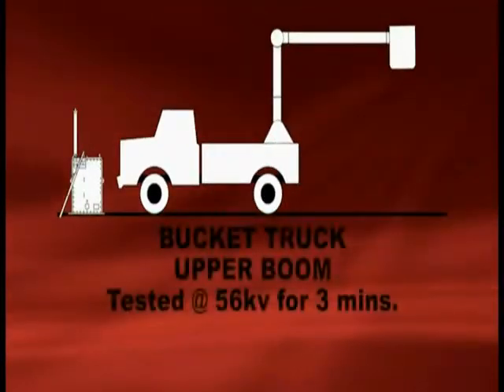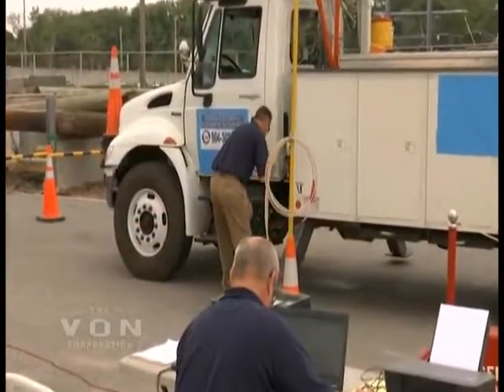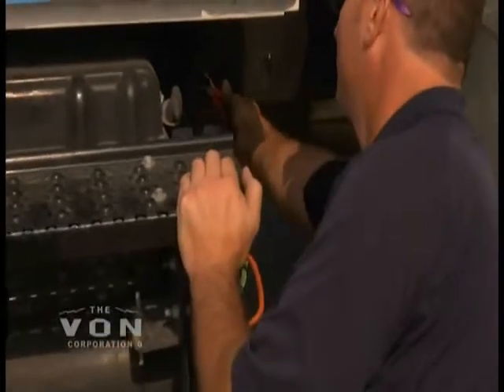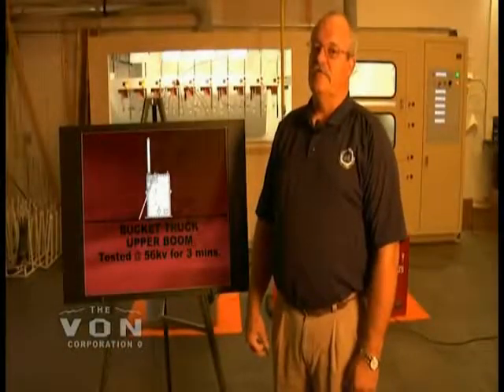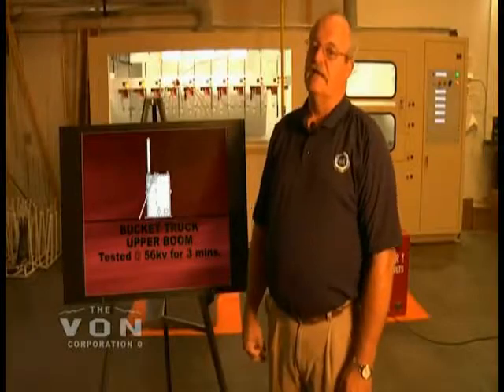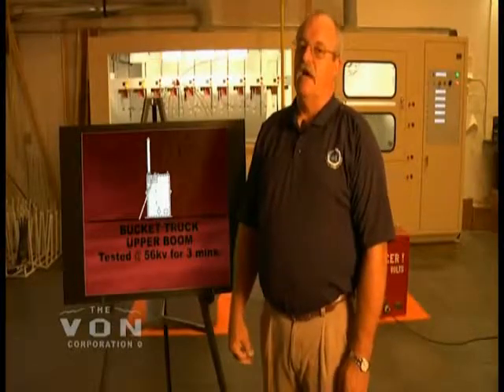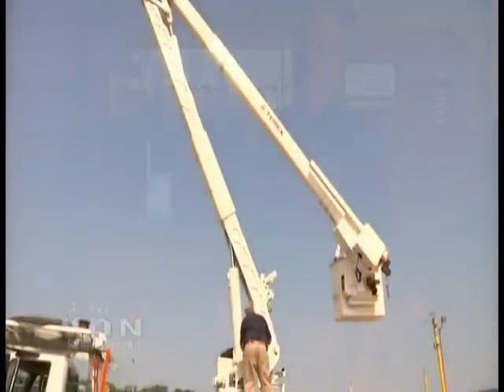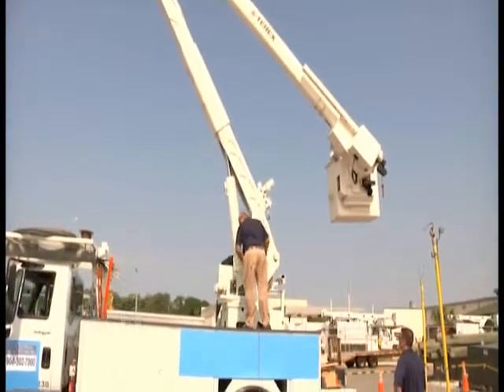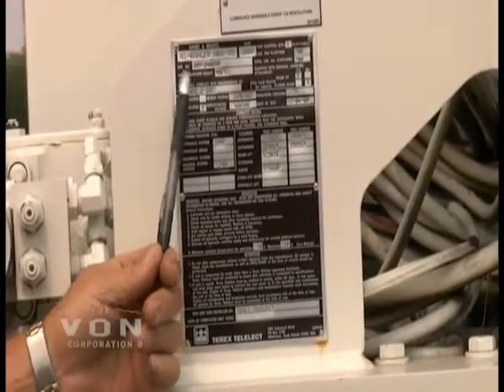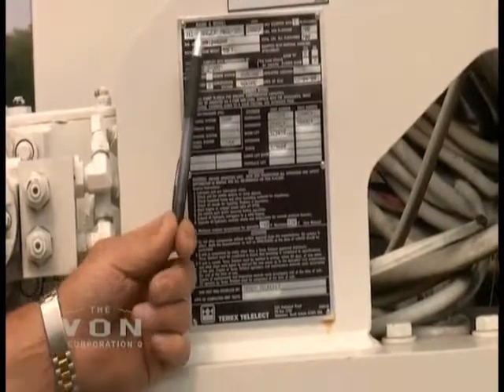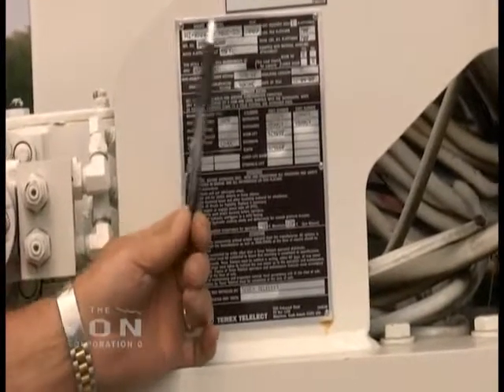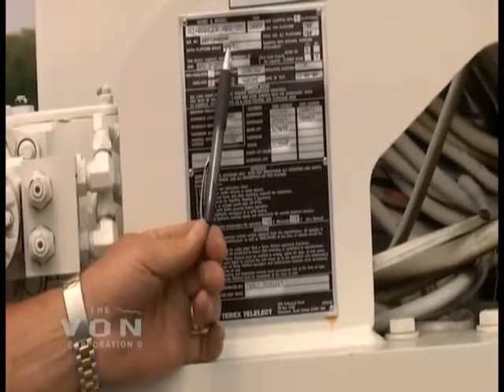Now we're going to test a bucket truck so that it conforms to ANSI A92.2 standards that has been mandated by OSHA in 1926. Insulated aerial lift devices have 3 primary insulating systems. You have the upper boom insulator, the lower boom or chassis insulator, and the bucket liner. This nameplate tells us how to test this bucket truck. The information that is on it is the manufacturer, model, year it was manufactured, serial number, maximum height and maximum load.